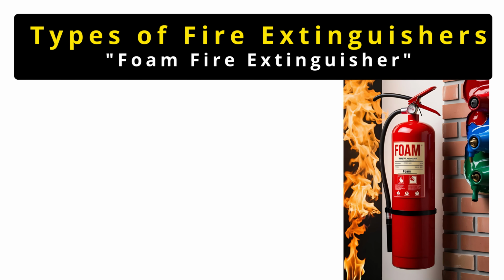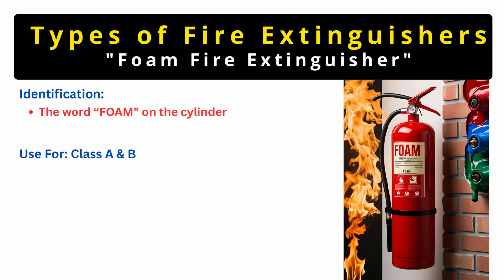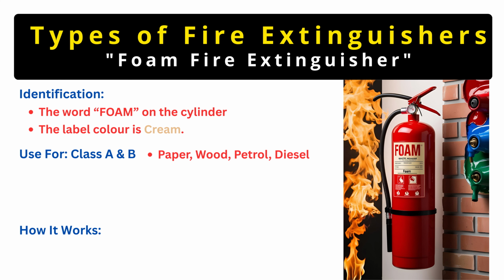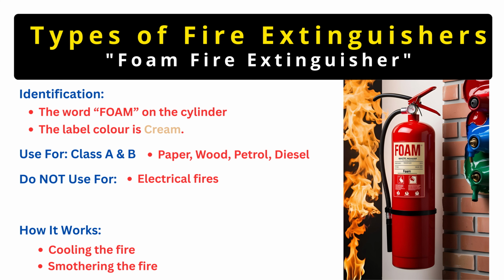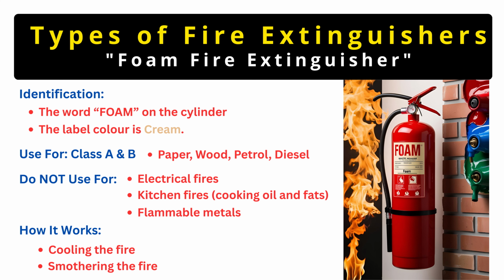Now let us understand the foam type fire extinguishers. Foam extinguishers are mainly used for Class B fires, but they can also be used on Class A fires because they are water based. Foam extinguishers can be identified by the word foam on the cylinder. The label color is cream. Foam extinguishers are used for Class A fires and Class B fires. Class A fires means paper, wood, cardboard, and Class B fires means petrol, diesel, paint, flammable liquids. Foam works in two ways: cooling the fire and smothering the fire. It forms a foam blanket on the surface of the burning liquid, cuts off the oxygen and stops the fire. Foam extinguishers must not be used on electrical fires, kitchen fires and flammable metal fires.